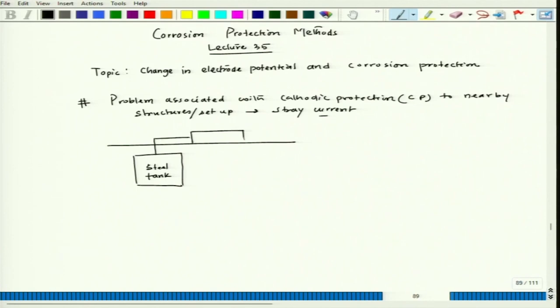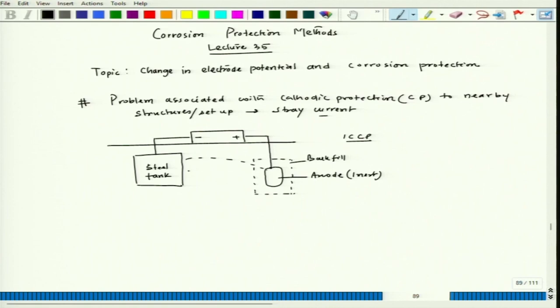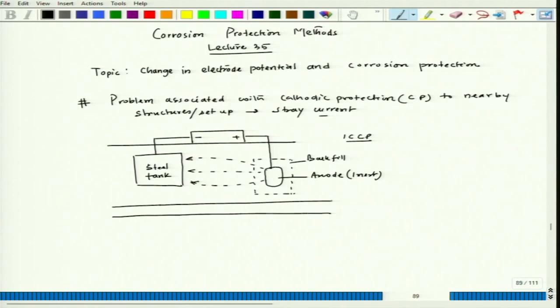We have a DC power source with a negative terminal and a positive terminal. There is one inert anode with backfill surrounding it — this is a typical ICCP setup. Current enters the steel part from the anode. Now let us say there is another pipeline running just below this ICCP setup.